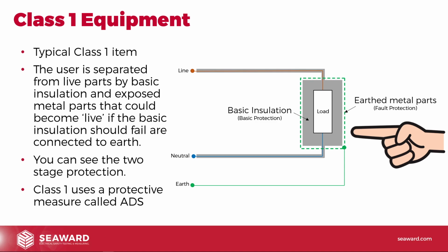Whereas in something like class 0, remember from the previous slide, we only had basic insulation. There was no additional layer of protection there. There was no fault protection. So if something had gone wrong with the basic insulation, you're on your own. It's tough luck really. So this is where class 1 comes in. Normally, class 1 equipment is equipment that's got a significant amount of metalwork on it. It's got a metal case. And the way we're protected from that metalwork is by connecting it to earth.